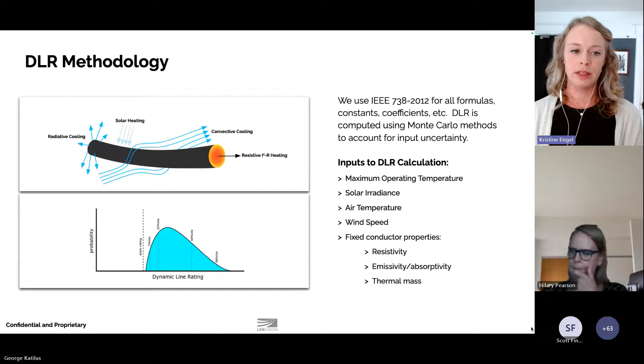a confidence interval. So we have tools as well to assess things like what does a certain percentile selection mean for your conductor temperatures? If you were to operate at that level the entire time, would you have an exceedance of the maximum operating temperature? How severe would that be? How long would it last? And we can compare that really against the existing rating methodology, whether that's static ratings or ambient adjusted ratings. There is, of course, going to be some risk inherent to those static or ambient adjusted rating methodologies because wind is sometimes quite low. And we do see that with dynamic line ratings as well. Next slide, please.